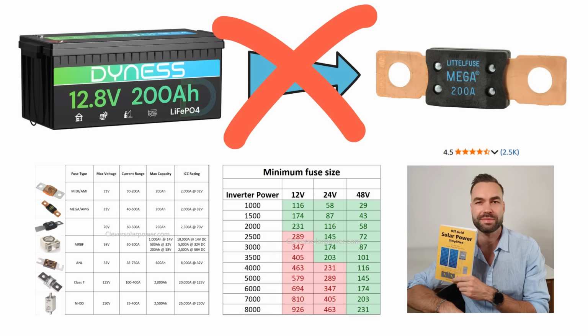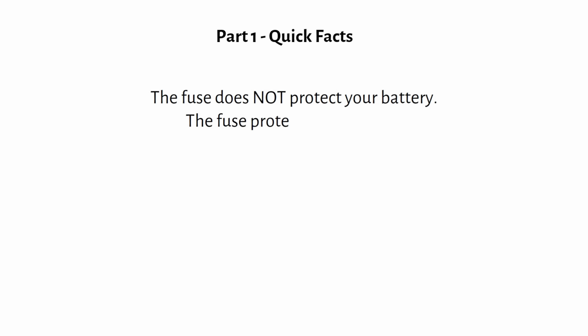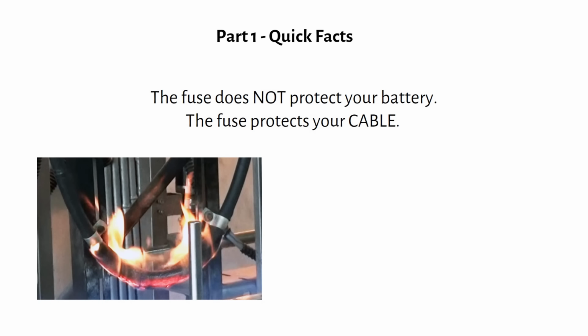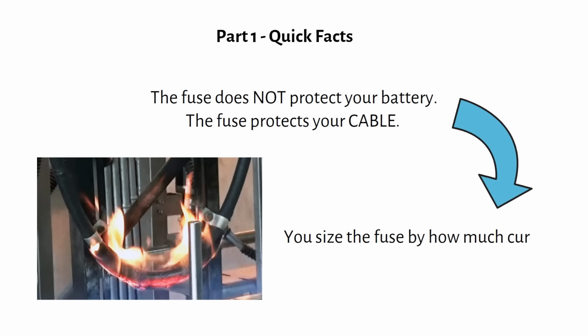Ready? Let's get started. The fuse does not protect your battery. The fuse protects your cable. The fuse needs to blow before the cable turns red and starts a fire. So you do not size the fuse based on battery capacity. You size the fuse by how much current your inverter draws from the battery.